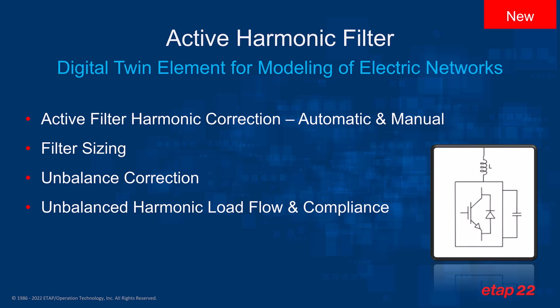ETAP 22 also includes a new digital twin element for modeling of electrical networks, which is the active harmonic filter. Active harmonic filter essentially allows us to do two things. One is correct the unbalance in the system, as well as power factor correction, and it also allows us to filter out harmonics in an automatic or manual manner.